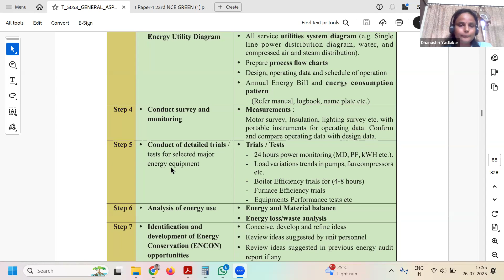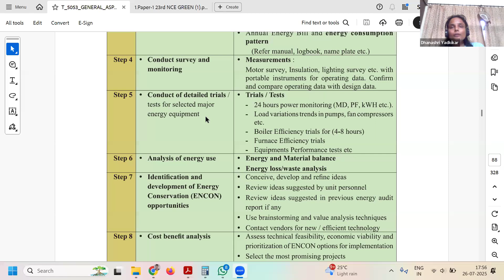So the next step is step 5, conduct of detailed trials. You are taking the trials and tests. That means 24 hours of power monitoring: maximum demand, power factor, units consumption, harmonics. You can collect it with the help of a power analyzer, 3-phase or single phase, and load variation trends in pumps, fans, compressors, etc. Then boiler efficiency trials, furnace efficiency, or many other equipment efficiency. So conduct of detailed trials means you are now taking the efficiency test of various equipment, and collecting the power consumption data of various equipment.